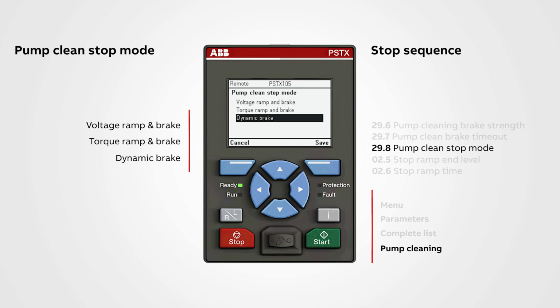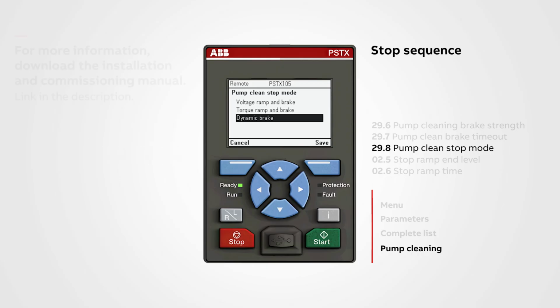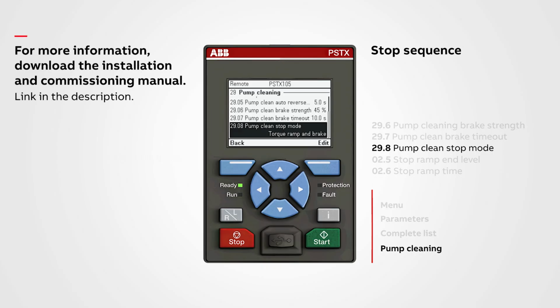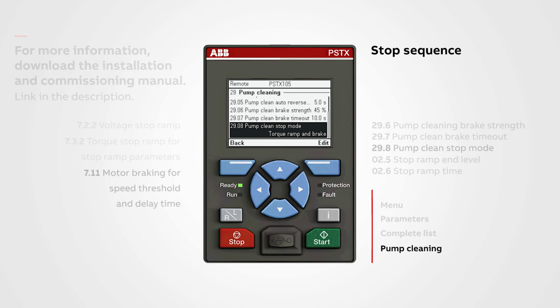These 3 stop modes will have various effects on the pump cleaning strength. The torque ramp and brake will be the softer stop mode, and the dynamic brake will have a stronger cleaning effect but be more harsh to the system. For more information, download the installation and commissioning manual. See Chapter 7.2.2 Voltage Stop Ramp, 7.3.2 Torque Stop Ramp for stop ramp parameters, and see Chapter 7.11 Motor Braking for speed threshold and delay time.